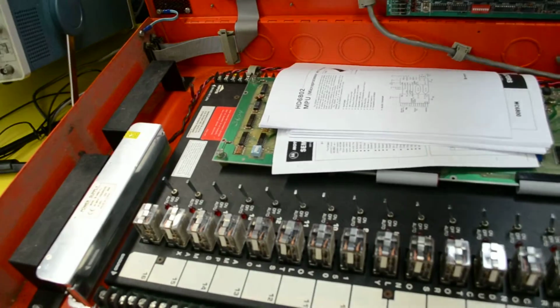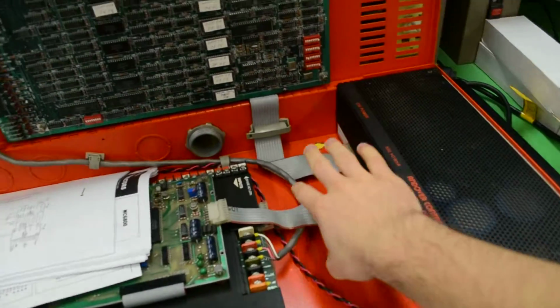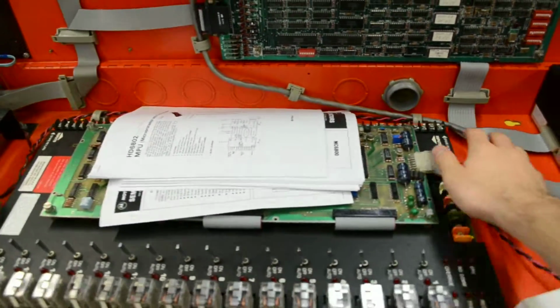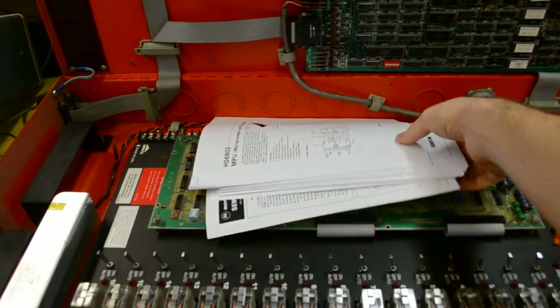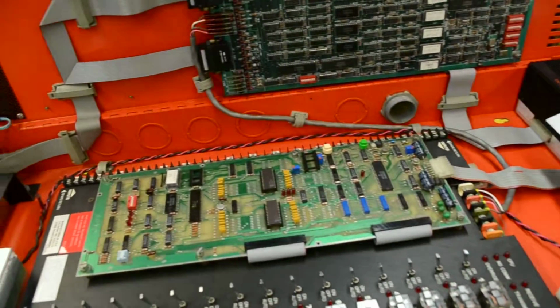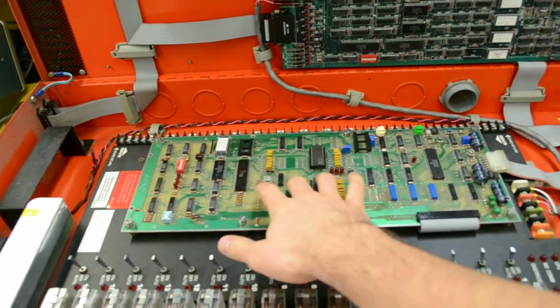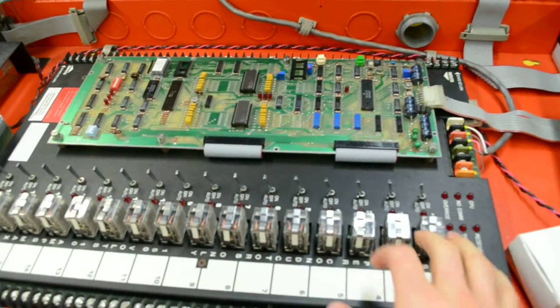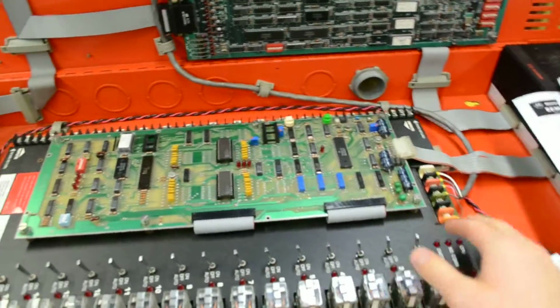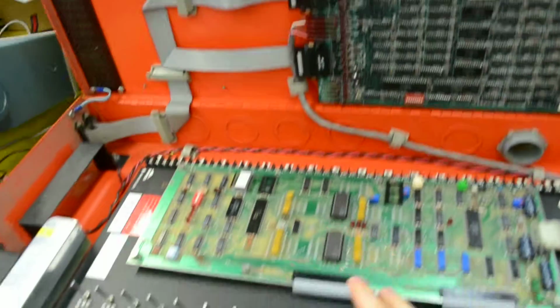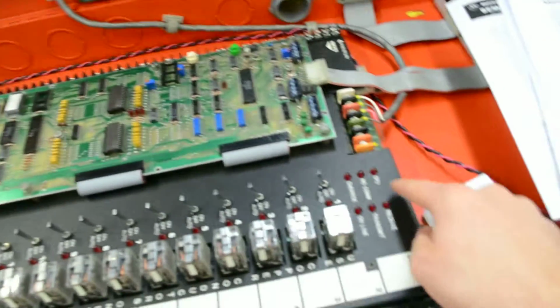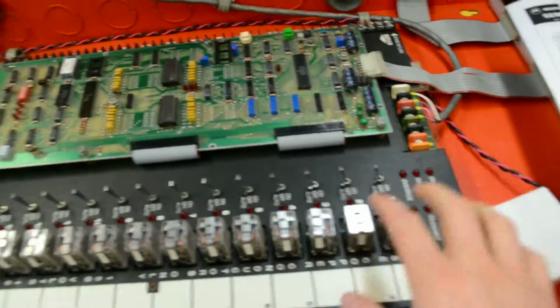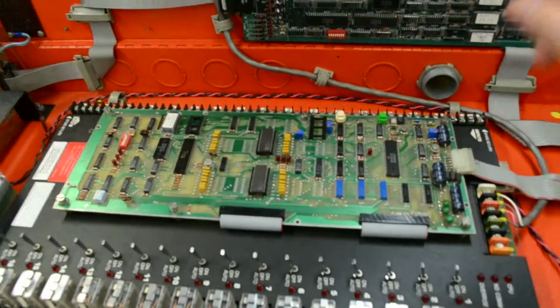We have discovered that the power supply is clean. There's nothing wrong there. The input-output longboard is not functioning properly on its own, and it should be able to run without the serial communication hooked up, and it should just run with CPU and say no COM and have everything off. It's not.